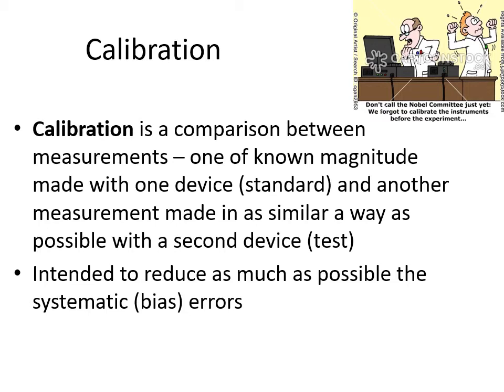Calibration is a comparison between measurements: a known magnitude measured with one device — the standard — and another measurement made as similarly as possible with a second device. We send sensors back to Campbell Scientific regularly to get recalibrated. The goal is to reduce systematic bias-type errors as much as possible. It won't remove random errors, since it's through multiple measurements that you compare the standard against the second device.